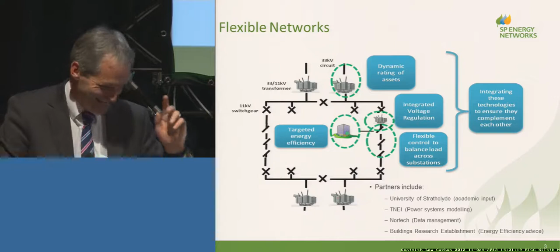This is dynamic thermal rating for overhead lines. One of the obvious things, when you think about it, is that the main constraint on overhead lines is they overheat, they get too hot. When they get too hot, the conductors stretch and start to lower, and you get issues with the lowering conductors. So the thermal capacity of the system is one of the key things.